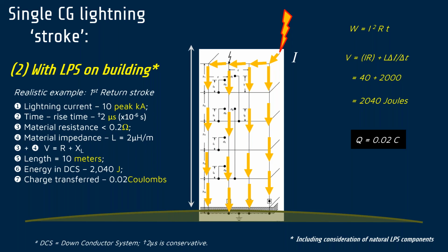Now, that's not the case with a paper mill, a factory, numerous examples. There is not necessarily a layered approach, where we've got a backup for the values below 16 kiloamps. I'm not sure that we've got a backup for the values below lightning protection level 3. And this is a concern, and I apologize for pausing here and just talking as opposed to showing you illustrations.